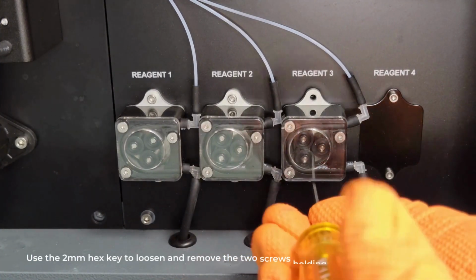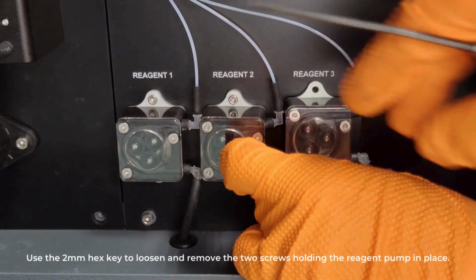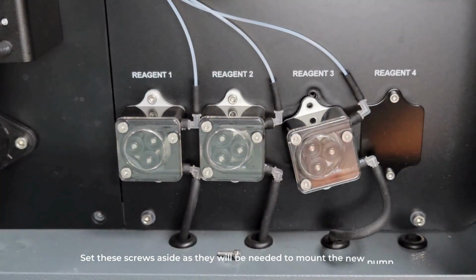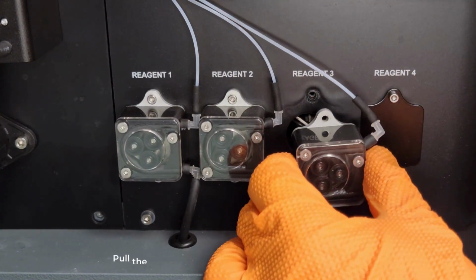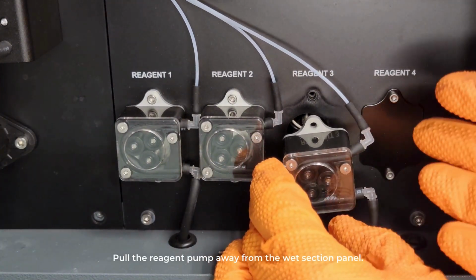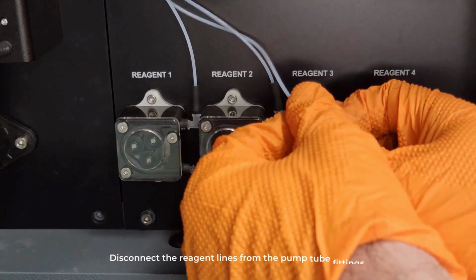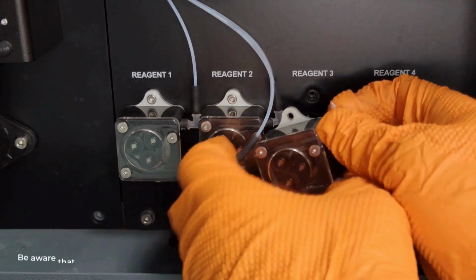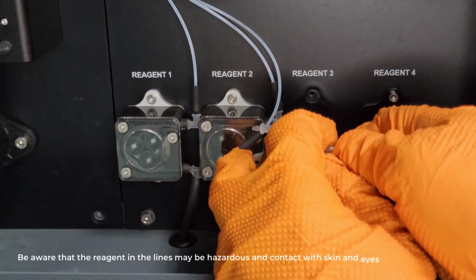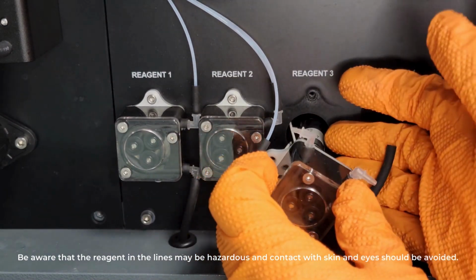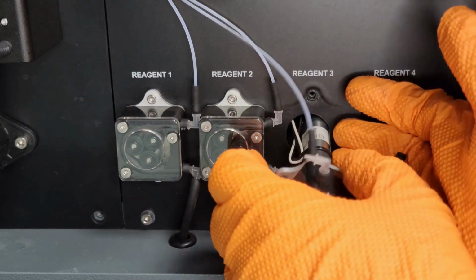Use the 2mm hex key to loosen and remove the 2 screws holding the reagent pump in place. Set these screws aside as they will be needed to mount the new pump. Pull the reagent pump away from the wet section panel. Disconnect the reagent lines from the pump tube fittings. Be aware that the reagent in the lines may be hazardous and contact with skin and eyes should be avoided.